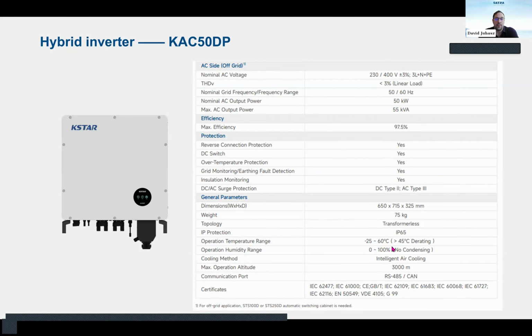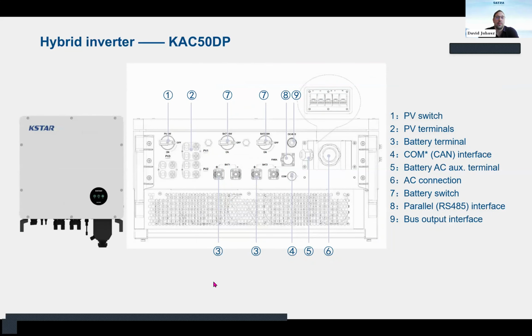The device is IP65, so it's dust-proof and waterproof. Regarding the communication port, it communicates with the BMS and the EMS with the RS485 and CAN protocols. This is the bottom of the hybrid inverter. You can see the PV switch, the PV terminals, and the battery terminals, 2 pieces. It has the communication interface and the parallel interface for RS485, which is here. So these 3 are the communication terminals of the inverters.